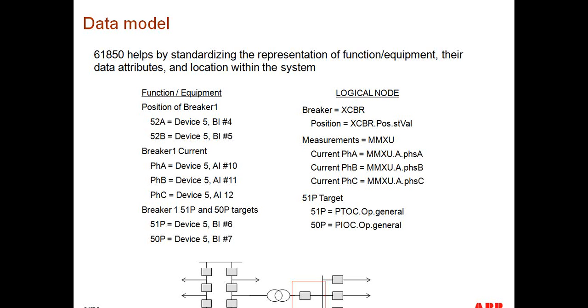This naming convention also, and we'll keep this in mind, and I'll remind it throughout the presentation, now makes it much simpler to exchange information from one relay onto the other in digital form. And the reason for that is because if we were to look at a GOOSE message that's incoming to a particular device, you're not going to see binary input 5 or binary output 6 or bit number 7 that's either a 1 or a 0.